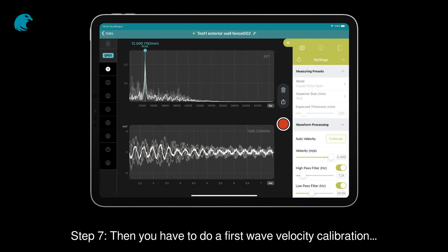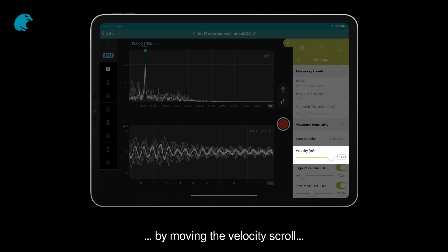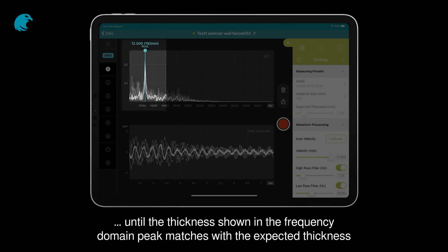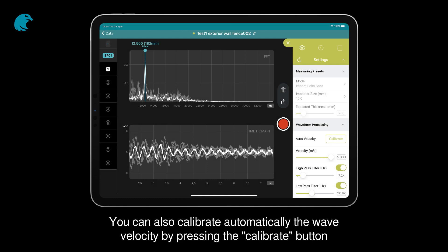Step 7. Then you have to do a first wave velocity calibration by moving the velocity scroll until the thickness shown at the frequency domain peak matches the expected thickness. You can also calibrate the wave velocity automatically by pressing the calibrate button.